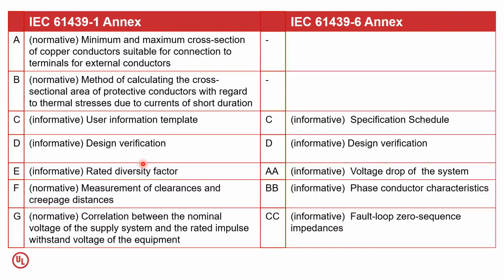This is a very valid point that people ask: why is this design verification made informative and not normative? That is again because, suppose you want to comply to a standard, you have various means to comply. You could do it all by testing, or sometimes you could prove it by means of a reference design, or sometimes you, as a regulator, could choose, I only want a short circuit, I only want to use a temperature rise for my determination. So that is why this has been made informative. Similarly, diversity factor, the manufacturers could use depending on what diversity factor they want.